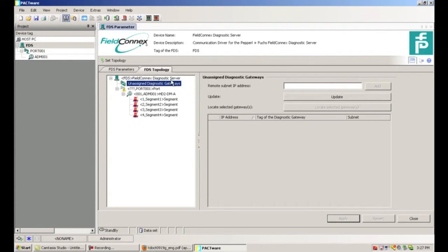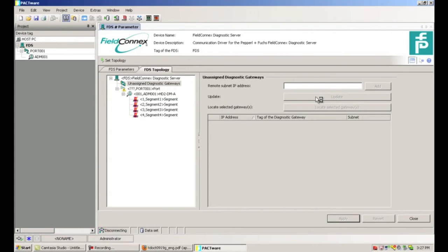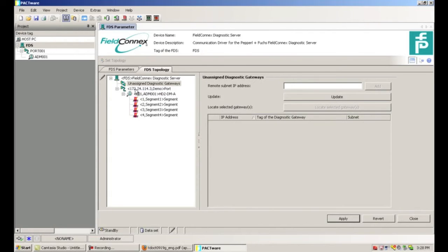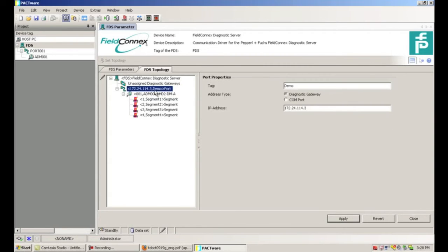The first step in assigning an Ethernet to RS-485 converter is to click on Unassigned Diagnostic Gateways and click Update. This will go out and search for all of the diagnostic gateways on our network. We can see here the 172.24.114.3 — this is the demo converter we have connected. The easiest way to bring this into the project is to click on it and drag it over to the appropriate port. Now you can see the port has the IP address and tag of the RS-485 to Ethernet converter in our demo setup. This can also be done by clicking on the port and entering the tag and IP address manually, but drag and drop is easier.